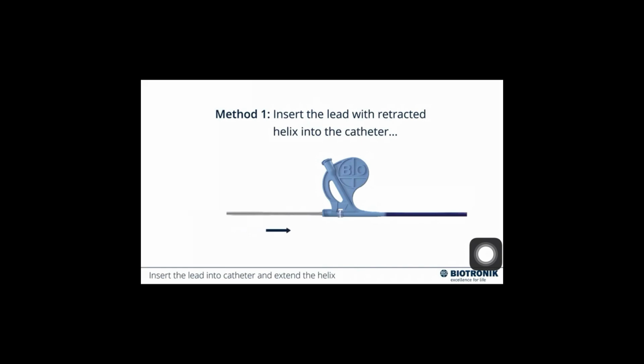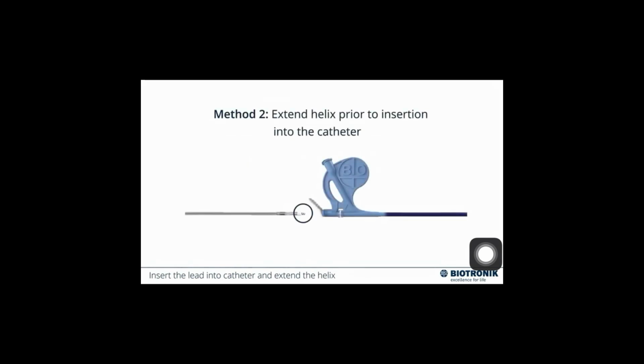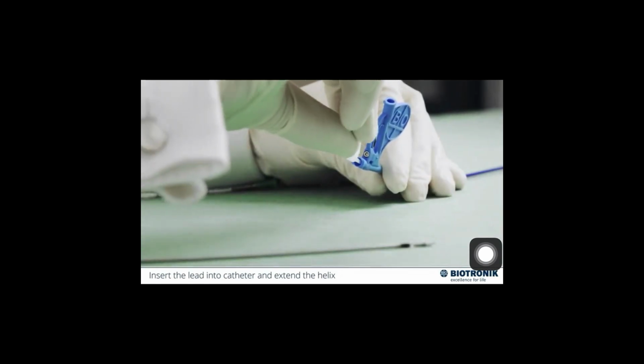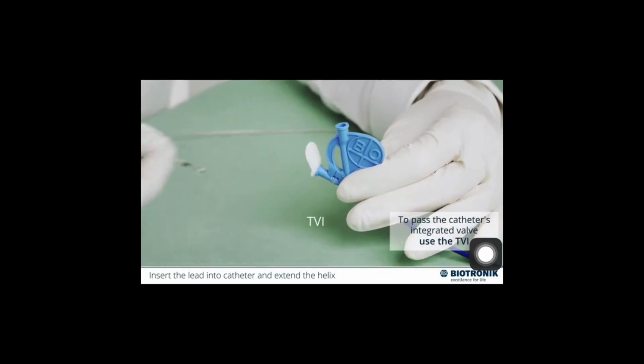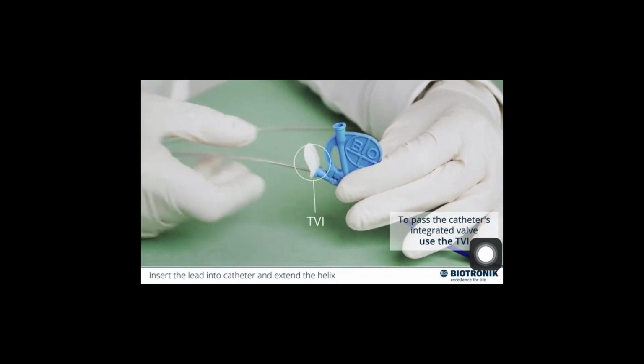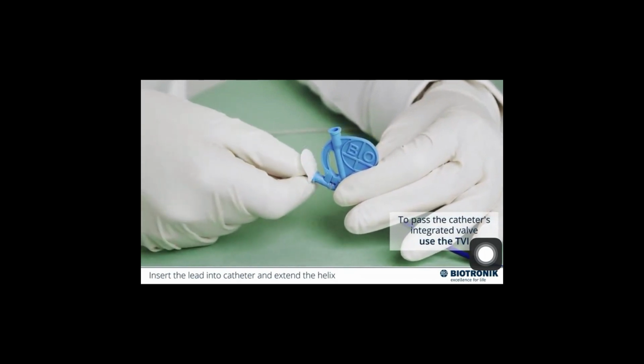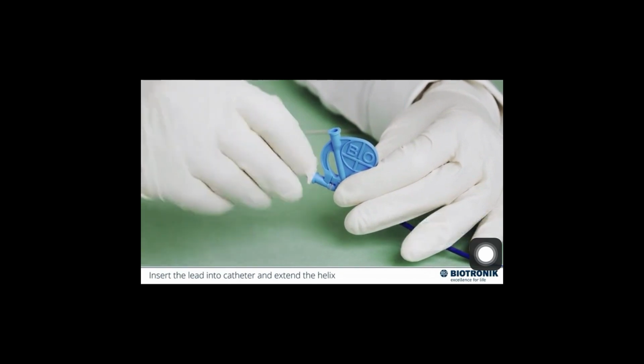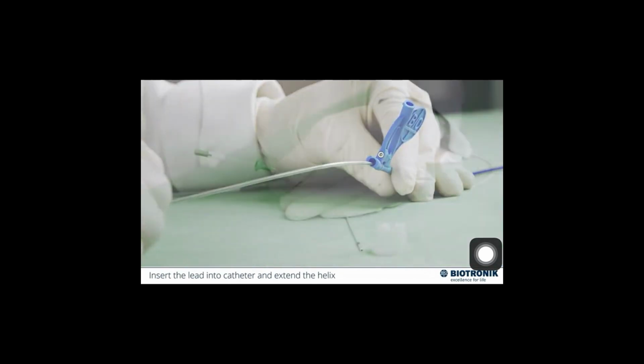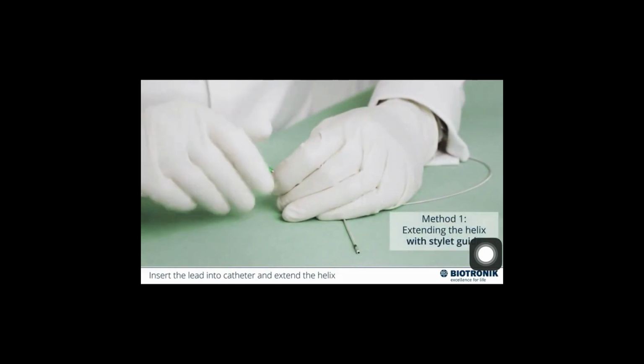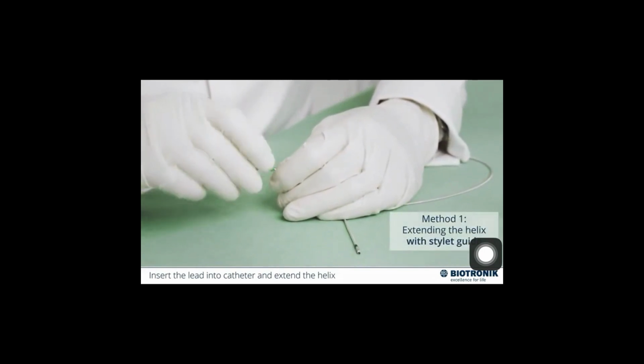Either insert the lead into the catheter and whilst checking under X-ray, extend fully the helix inside the catheter. Or alternatively, expose the helix of the lead before inserting the lead into the catheter. Use the transvalvular insertion tool to safely insert the exposed helix past the integrated valve of the catheter. For exposing the helix, use the fixation tool or the green stylet guide.